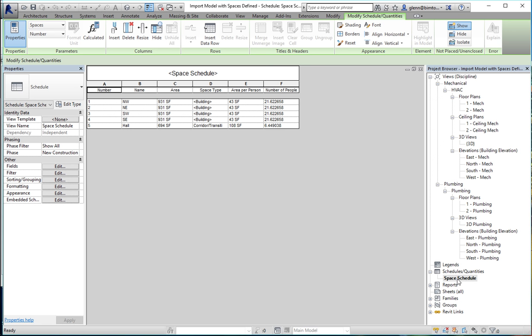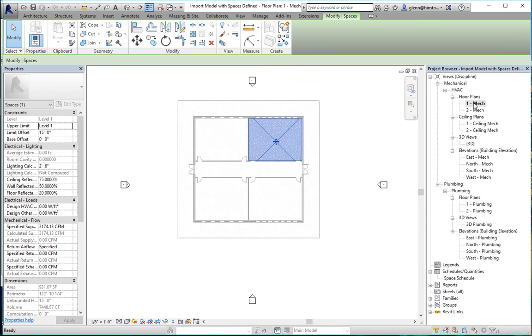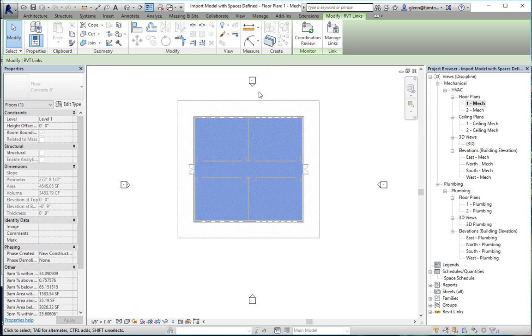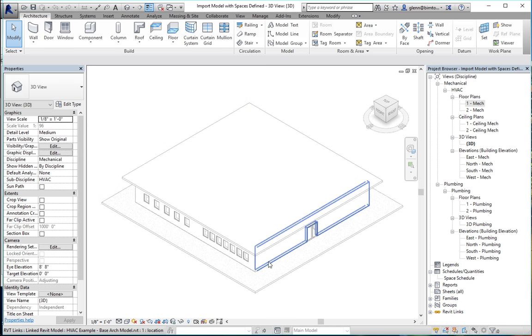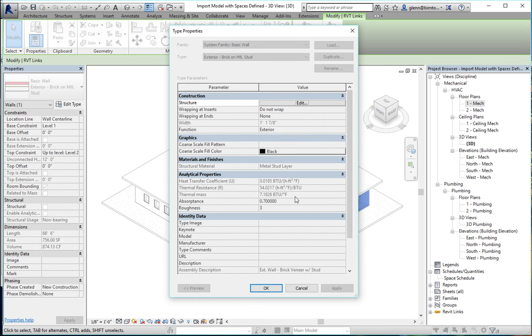All those people and the fresh air requirements associated with them feed into how much ventilation air we need. All those people are also generating heat, contributing to the cooling load — more people means more ventilation but also more cooling. The walls and roof have R-values and thermal properties associated with them. The combination of people, operating hours, outside temperature, and R-values all work together to figure out how much heating or cooling is necessary.